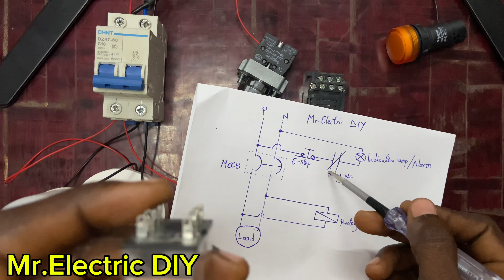Number 12 here and number 8 is normally open, and the same number 12 and number 4 is normally closed. So we are going to use number 12 and number 4 as our normally closed terminal on the relay socket.